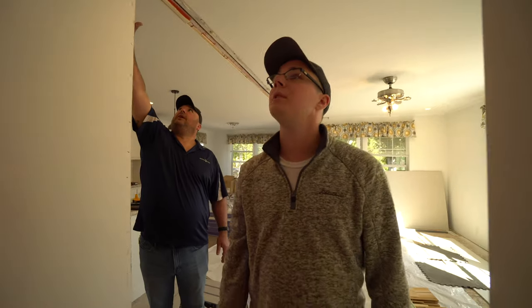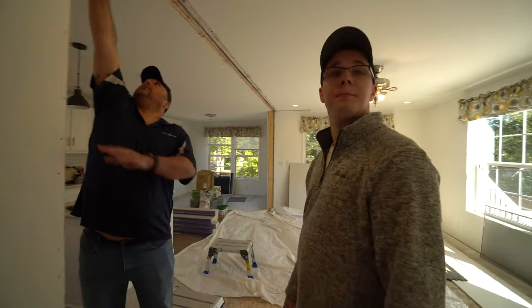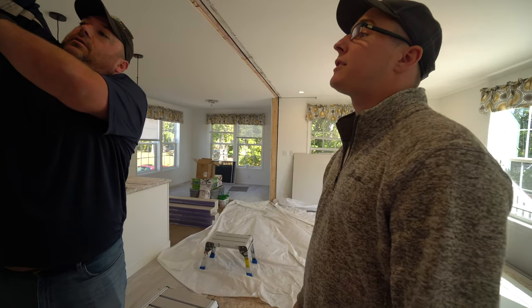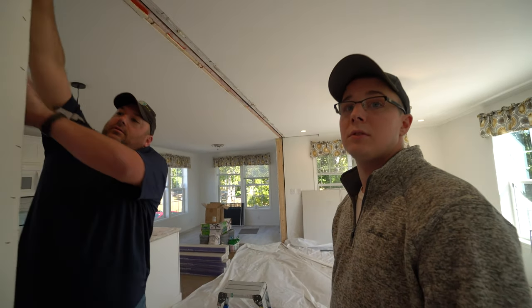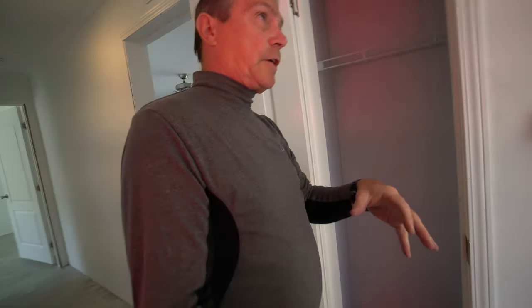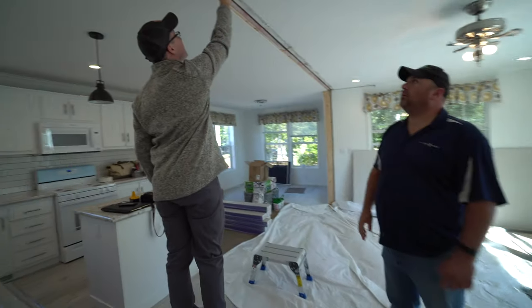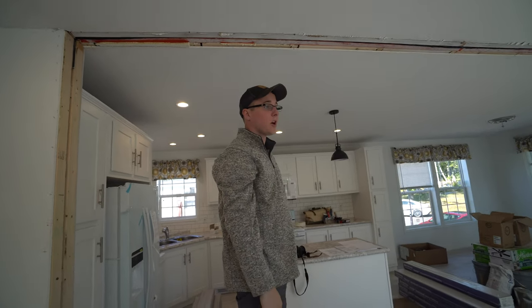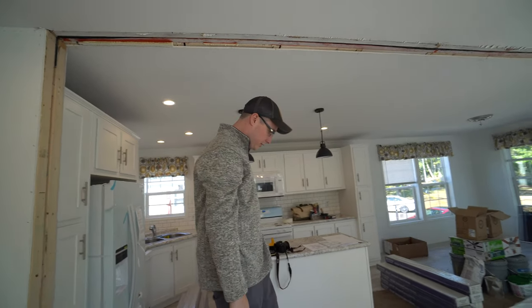So do you have to go around the house now and check different places where the air is coming through? Yeah. So is this a good day to do it when the marriage wall hasn't been sealed? Yeah, actually, that's a great opportunity. And what we'll do there is a positive test. You go through and use a smoke test to see if it sucks up any place where it's sucking. Yeah, you can feel some here. I just felt it up in the corner. And we're still at our targeted goal, so that's pretty good.